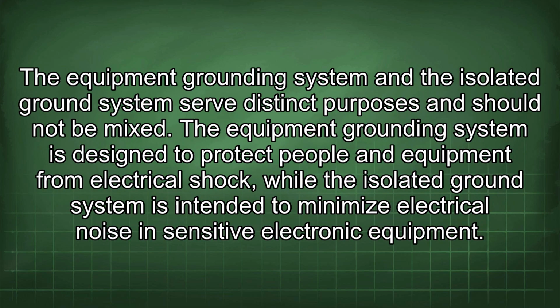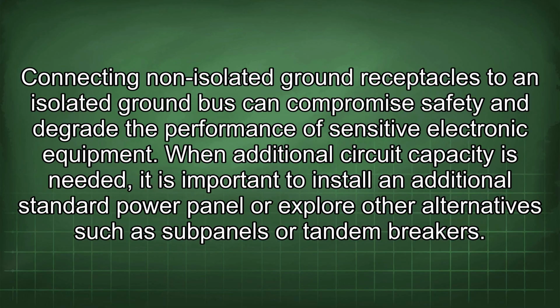The equipment grounding system and the isolated ground system serve distinct purposes and should not be mixed. The equipment grounding system is designed to protect people and equipment from electrical shock, while the isolated ground system is intended to minimize electrical noise in sensitive electronic equipment. Connecting non-isolated ground receptacles to an isolated ground bus can compromise safety and degrade the performance of sensitive electronic equipment.